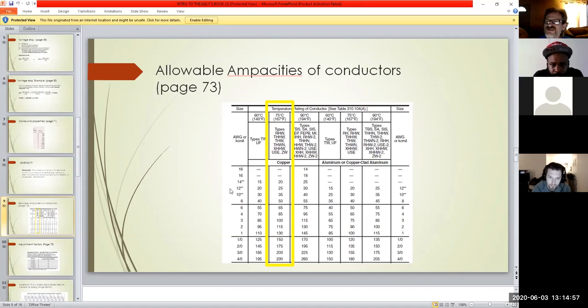The only time this changes is if the temperature changes. So if I'm out in Arizona, I'd be going up in this area, because heat changes things, and electricity does not like heat. The more heat there is, the less current I get. So when you're dealing in hot areas, you always have to go up in wire size. Our typical region for Illinois, we're pretty much running in this range here. If we go up to Alaska, then we go down. It all depends on the region you're in. But that's what they mean when they say ampacities - what your wire size can handle and what size breaker goes with that wire size.